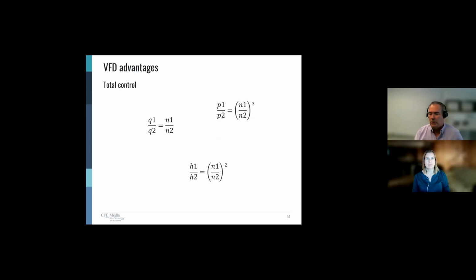We talked about total control, and where this really gets us some advantages is the fan laws, or the pump laws. We talked about flow being proportional to the shaft speed. Pressure, or head, is proportional to the square of the shaft speed. And power is proportional to the cube of the shaft speed. So if you think about it, if we can reduce the shaft speed by 5%, we cube that savings in power. This is good stuff. We can save real money here with VFDs.